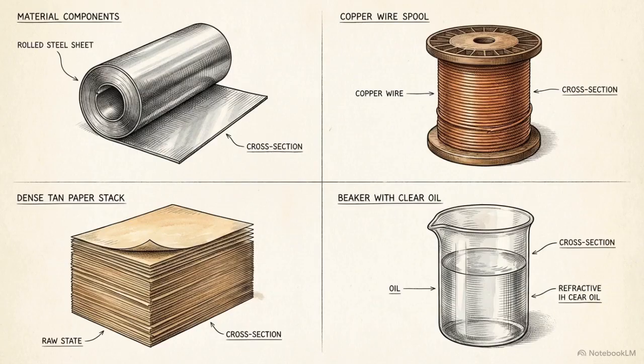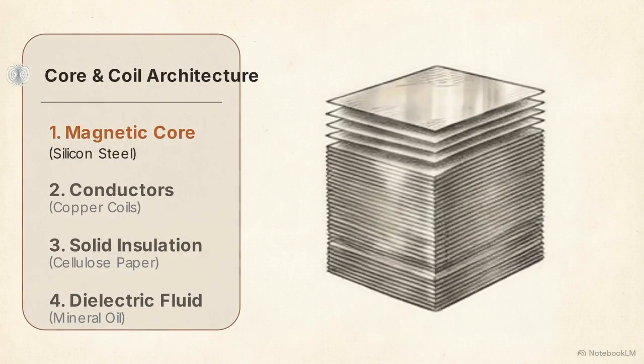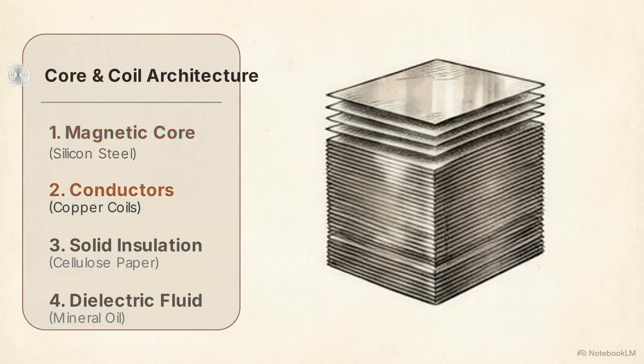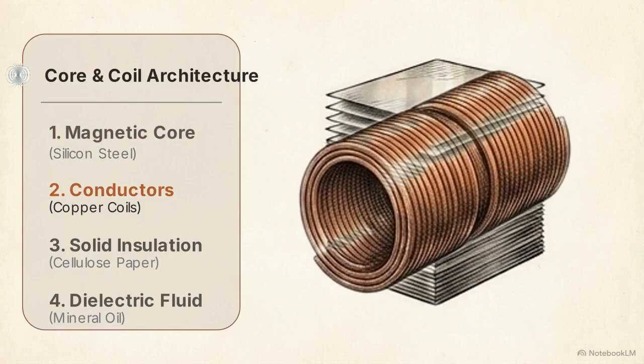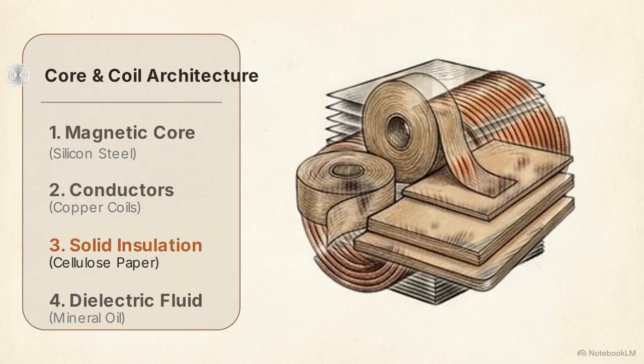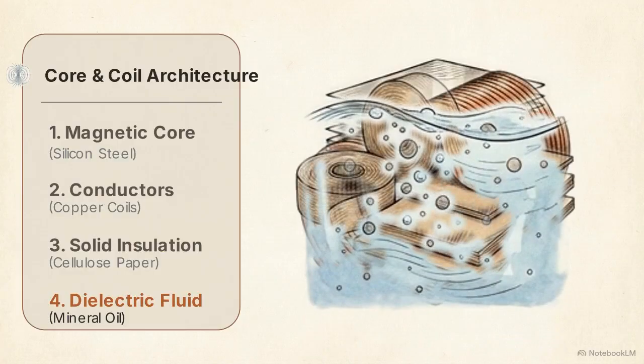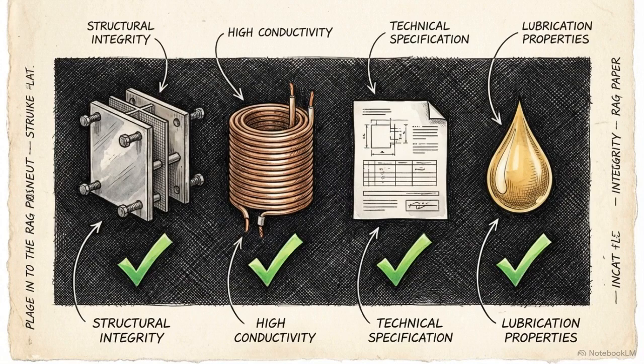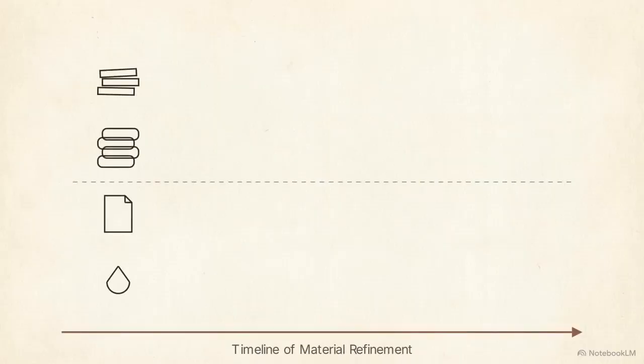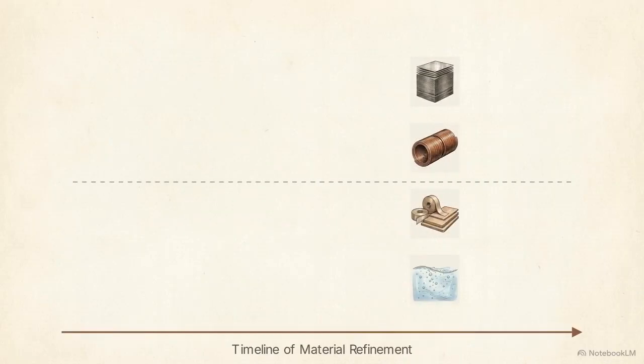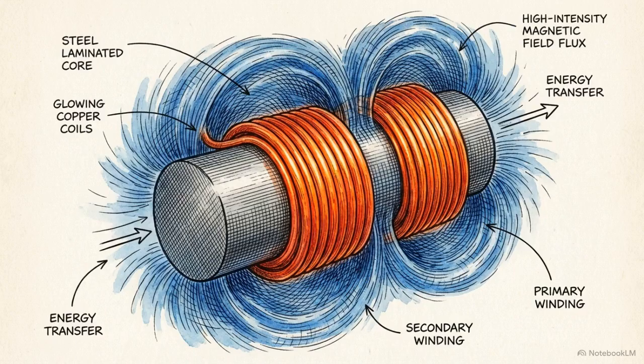The primary constraint of transformer engineering is building a static, high-voltage induction machine using only 4 foundational material groups. First, the core, thin plates of magnetic silicon steel stacked to minimize energy loss. Second, conductors, thick copper coils providing pathways for current. Third, solid insulation, dense paper separating windings from the core. Finally, dielectric fluid. The assembly is submerged in mineral oil. From a neighborhood utility pole to a cross-country transmission substation, no other fundamental components are required to execute the physics of the system. The entire history of transformer engineering is simply the refinement and optimization of these 4 materials to survive intense thermal and magnetic limits.